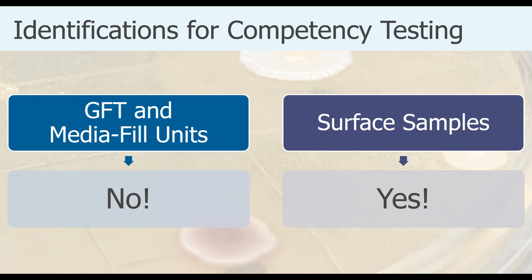The chapter now clarifies identification requirements for competency testing. For glove fingertip testing and media fill units with positives, you do not need to identify organisms to the genus level, and you do not need to identify positive media fill units. However, for surface samples taken during competency testing, the chapter refers to Section 6 on surface sampling, meaning identifications are required on any surface samples from competency tests. The action levels for surface samples after the media fill test are the same as those listed in Section 6.